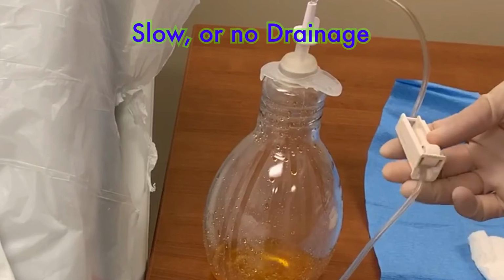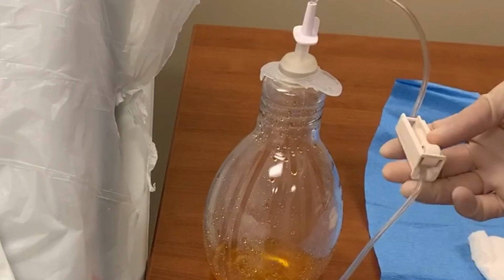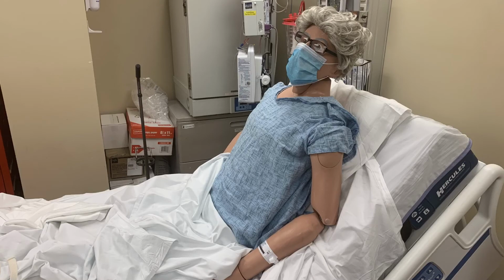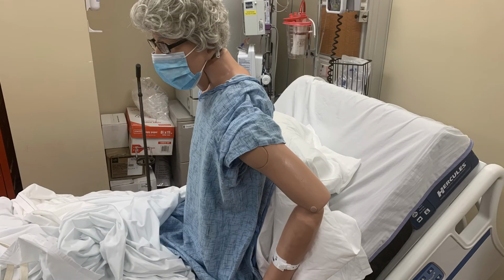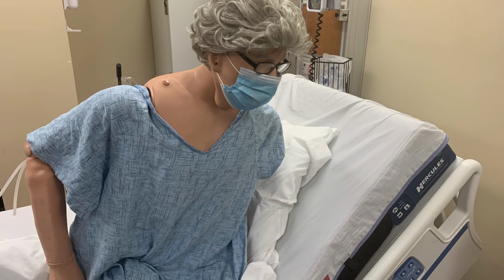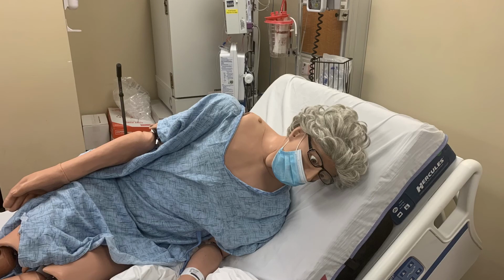If when you open the roller clamp, you notice that the system is draining slowly or not at all, it could mean that there is not enough fluid in the pleural space to drain, or it could mean that the catheter is in a position that is hindering its ability to drain the fluid. It's possible that the catheter is being pressed up against the chest wall. To dislodge the catheter, you may need to help your patient change positions. If this is effective in dislodging the catheter, you should begin to see fluid drain into the bottle.